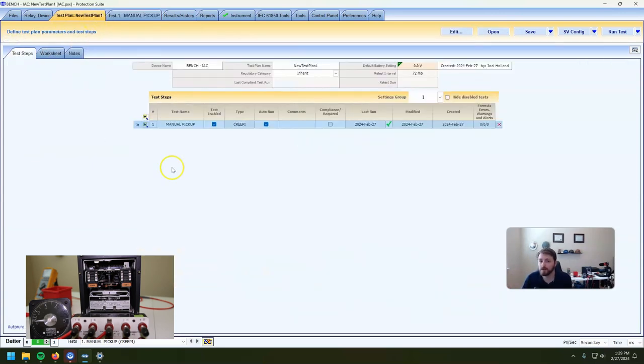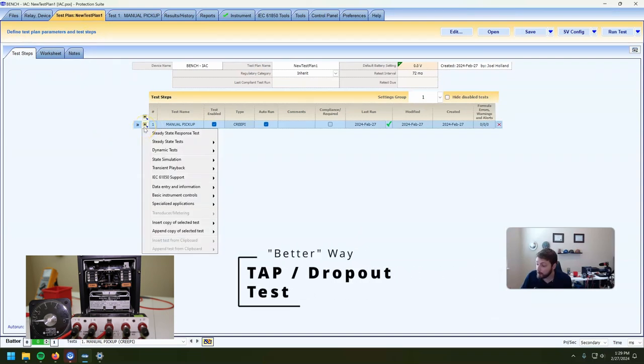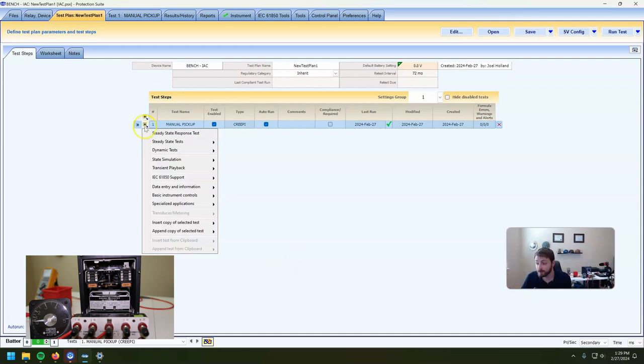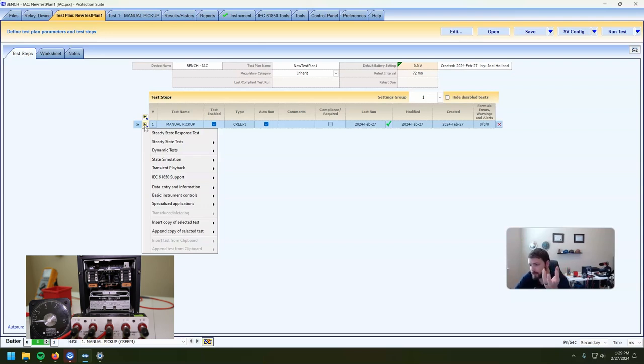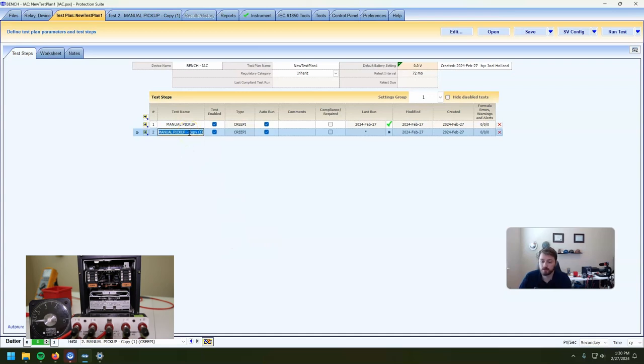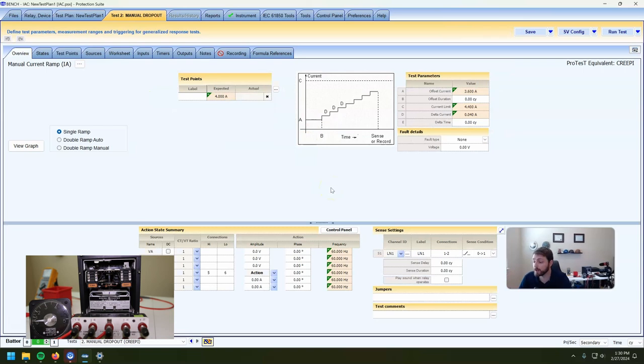What we can do is a dropout test. Instead of just watching the little line to see when it trips, we can set this up to see at what current it drops out at. The pickup amount should be the point where it has reached equilibrium with the reset spring, essentially. We're doing the dropout of the time over current element, not the instantaneous. This is not a required test, but it's just another way to determine what the pickup is going to be.